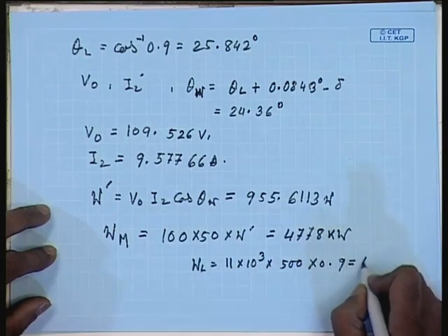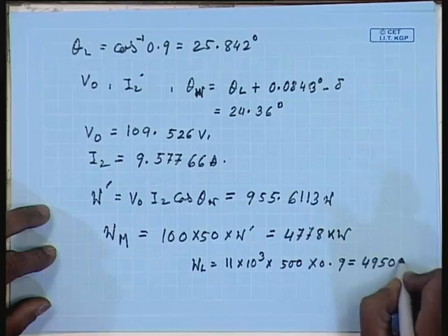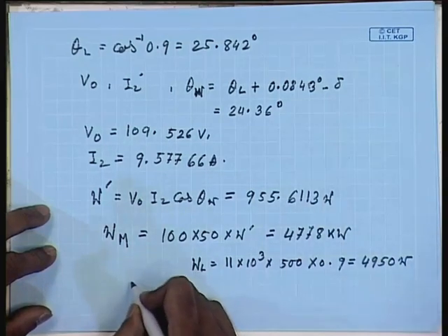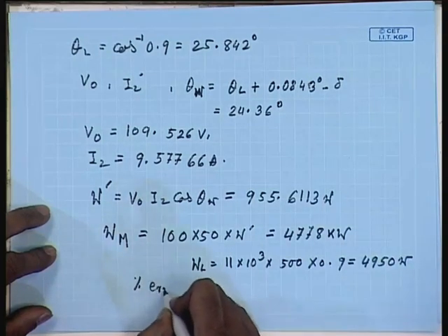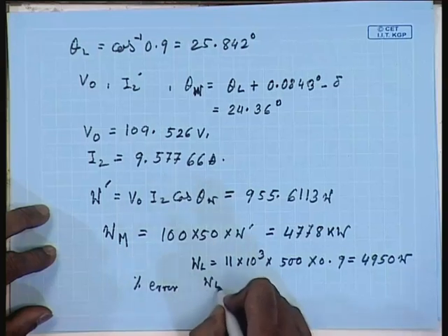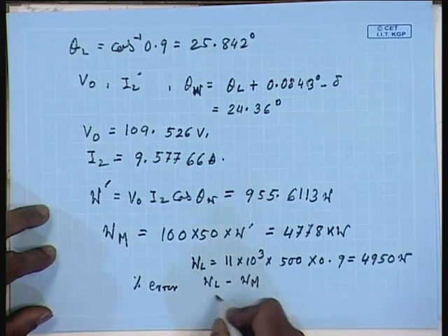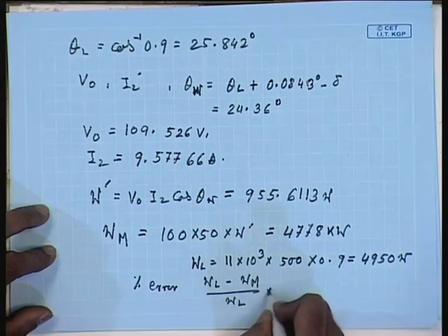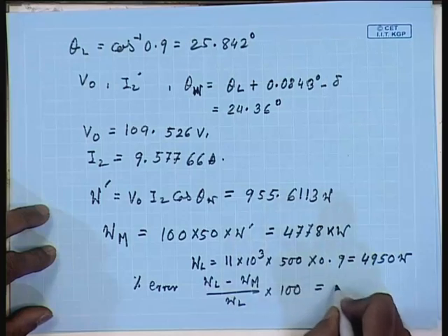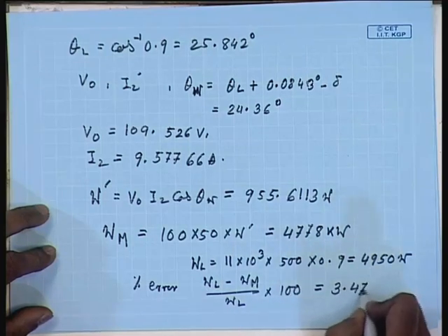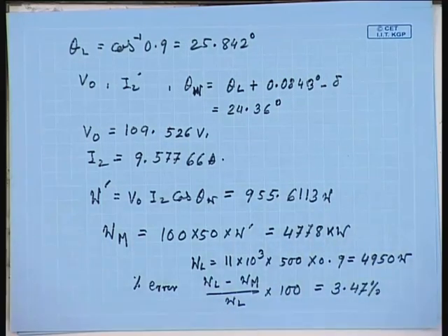This comes to 4950 watts. So, the percentage error due to this is WL minus WM by WL into 100. This comes to 3.47%, which is due to both angle error and the magnitude error of the CT and the PT respectively.